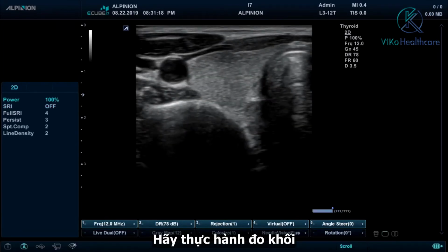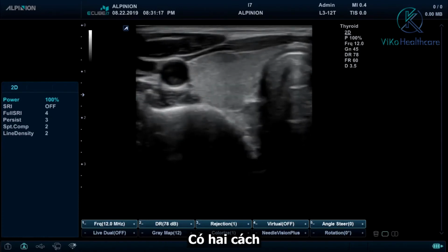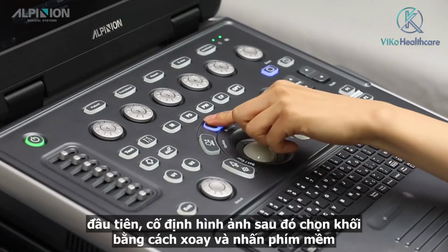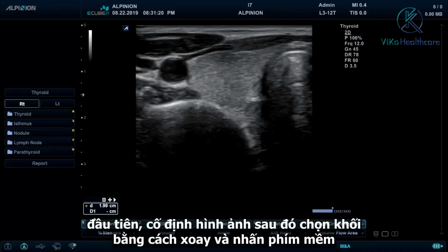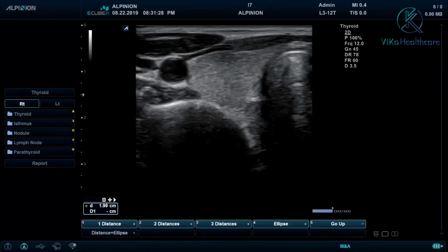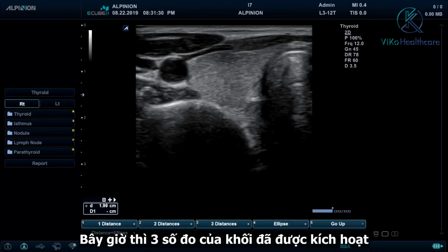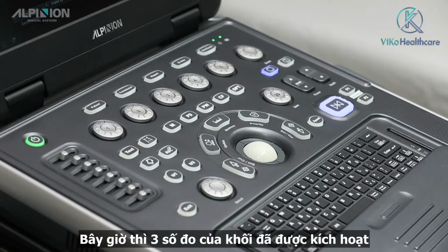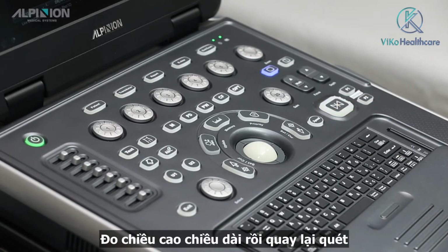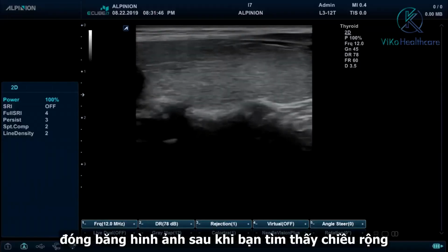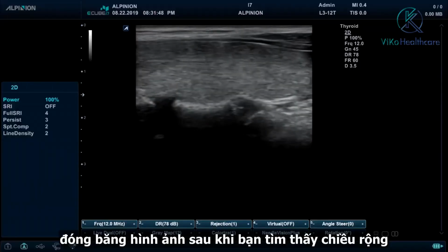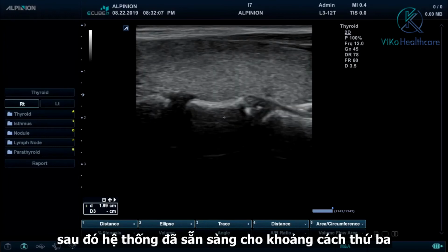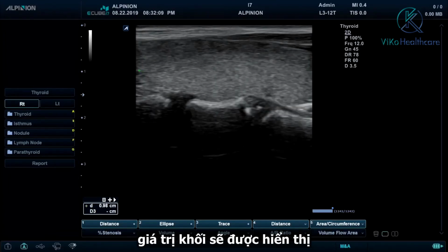Let's practice a volume measurement. There are two ways. First, freeze the image, then select volume by rotating and pressing the soft key. Now, 3 distance volume measurements are activated. Measure length height, then go back to scan. Freeze the image after you find width. Then system is ready for third distance. Volume value will be displayed.